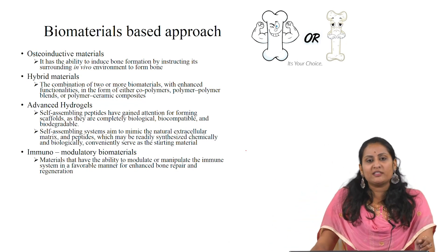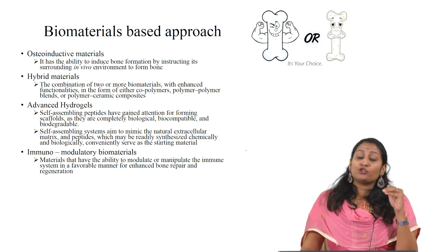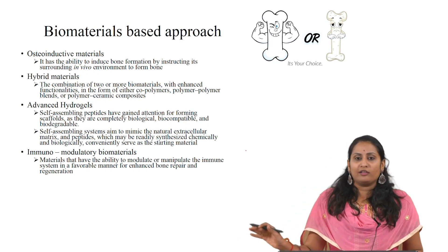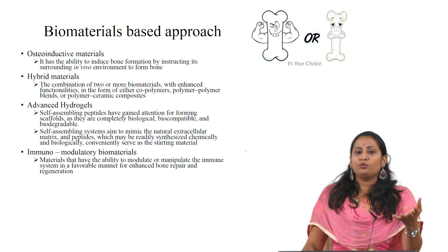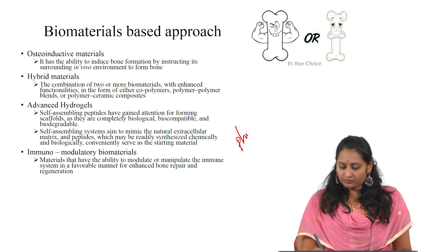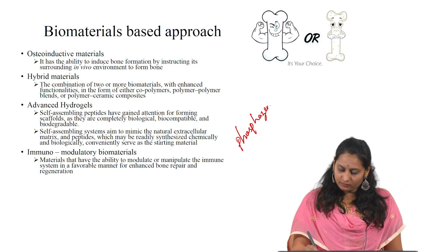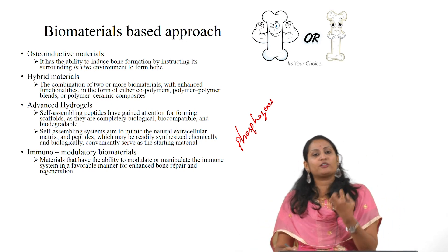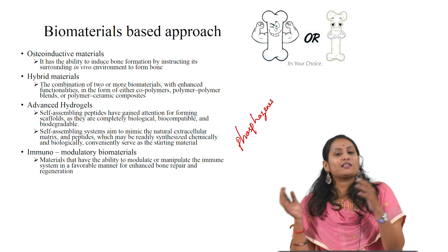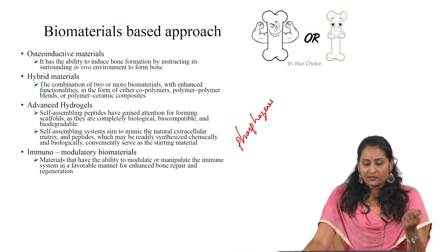The degradation product of PLGA is acidic in nature. Prolonged exposure of tissue to acidic degradation products will lead to tissue necrosis and eventually implant failure. To address this, researchers combine PLGA with a polymer like polyphosphazenes, whose degradation products are at neutral pH. By combining PLGA with polyphosphazenes, they develop a biomaterial that produces non-toxic degradation products.